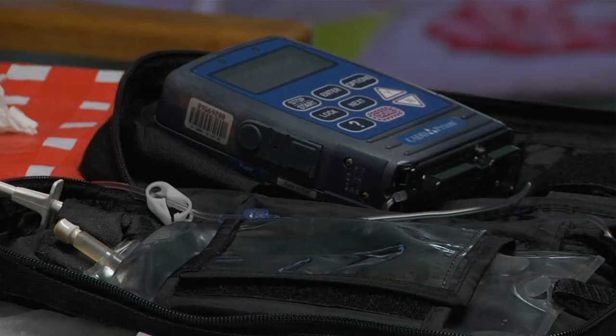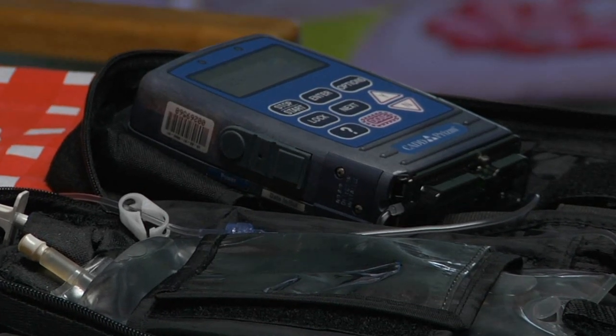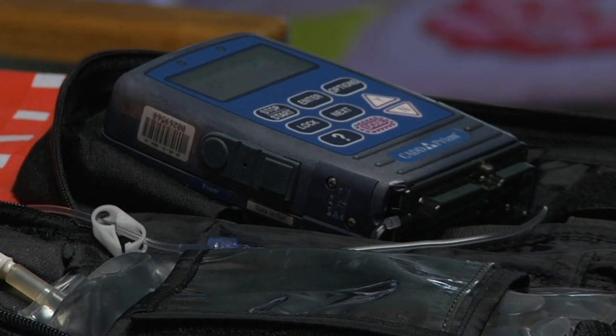One example he gives is called a key bounce. You go to punch in 20, but if the 0 is read twice, then the machine will deliver 10 times the intended dose. Depending on the drug, that error could be lethal. Sometimes the operators think they're the ones who are at fault, and we've gone back and we've looked at those adverse event reports, and we've determined that in a number of cases it's a problem with the design of the device, and that's one of the reasons we're coming out with this initiative.